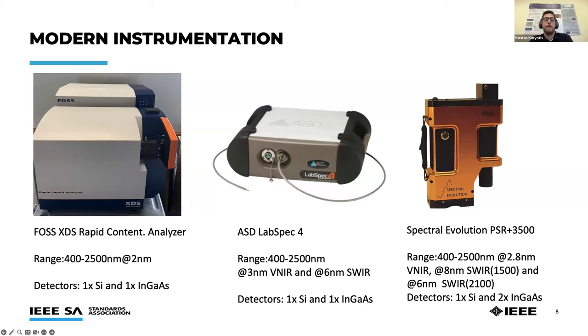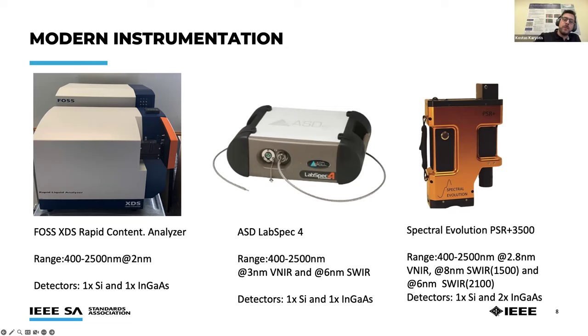I'll highlight three spectrometers. The first is the FOSS XDS Rapid Content Analyzer, used for developing the LUCAS soil spectral library, with two detectors and a nominal resolution of 2 nanometers. The second is the ASD LabSpec — and also the ASD FieldSpec — one of the best sellers used extensively for soil spectroscopy applications, with two detectors and nominal resolutions of 3 nm in visible/NIR and 6 nm in SWIR. The third is the Spectral Evolution PSR+ 3500, used by our laboratory, which can operate as both benchtop and portable, with three detectors and resolutions of 2.8 nm in visible/NIR, 8 nm at lower SWIR, and 6 nm at upper SWIR.